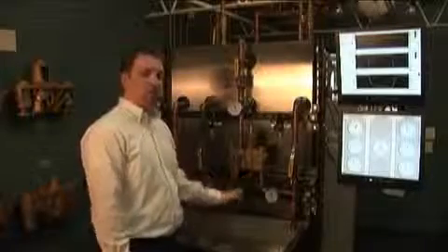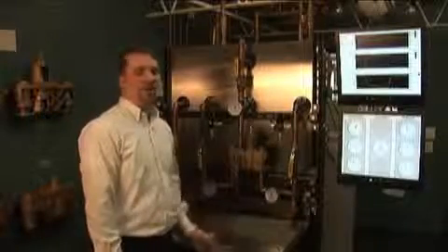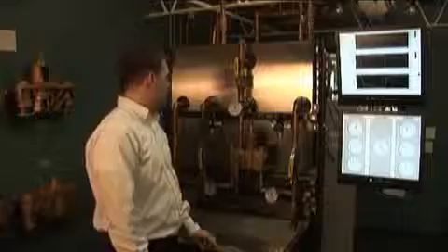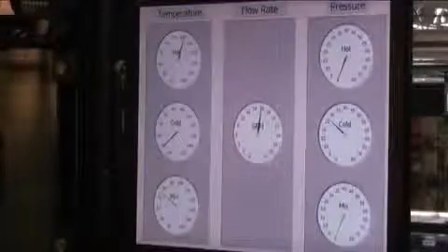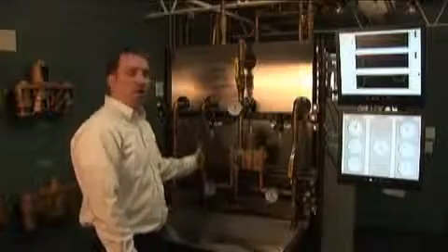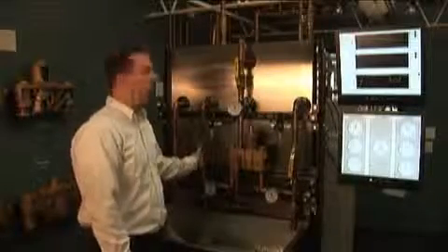But now what happens in an emergency valve if the hot or the cold are lost? This is really where it differs from a high-low thermostatic mixing valve. If the hot water is lost for any reason, we have an immediate supply of cold water still available. This is through a fixed cold water bypass built into the valve. We don't regulate how much cold water flows through the valve.